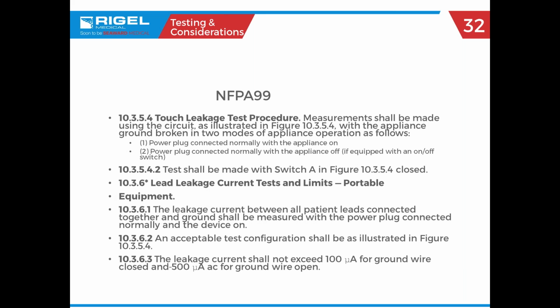Okay, so jumping a little bit more into the actual test procedure, we've talked about regular leakage current as well as lead leakage current. So this is where the real time saver comes into play with both the NFPA 99 and the 62353 standards. So remember we talked about how in 60601 each lead had to be tested separately, as well as lead to lead separately. And then those had to be tested in both conditions. So the good thing about the new standards is you're going to just tie all of the leads together and test them as one. So with that, the allowable range is just supposed to be less than 500 microamps, ground wire open, and 100 microamps with the ground wire closed. So that cuts out a lot of time and a lot of unnecessary steps.